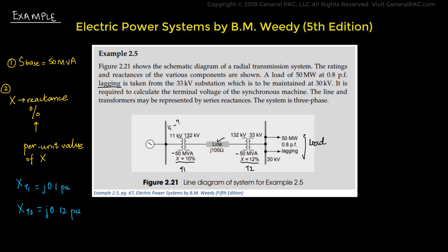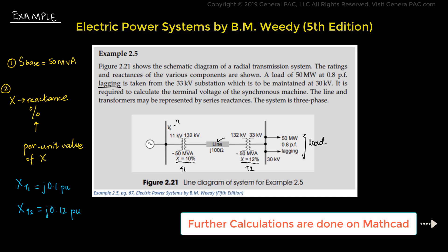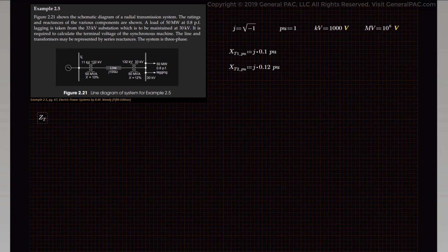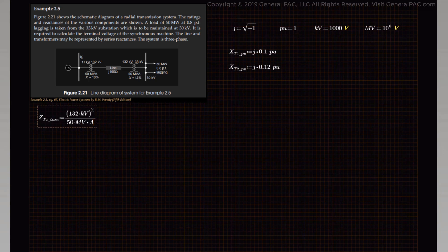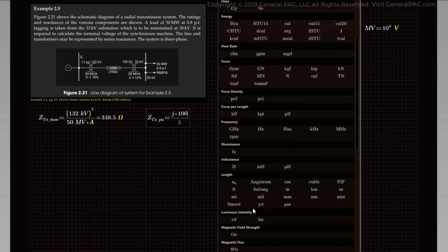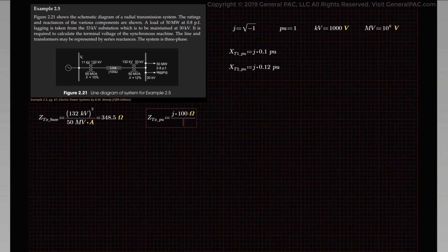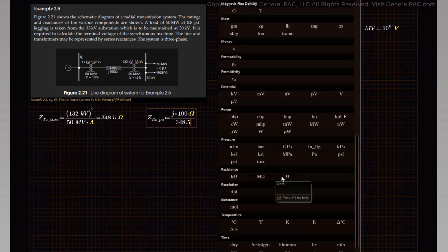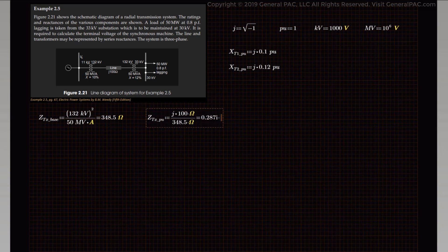Since we know the per unit impedances of the transformers, we can now calculate the per unit impedance of the transmission line. For the base impedance of the transmission line, the base impedance equals the base voltage squared divided by the base power. The base voltage being 132 kV squared divided by 50 MVA equals 348.5 ohms. The per unit impedance of the transmission line is simply the actual impedance divided by the base: J100 ohms divided by 348.5 ohms gives us J0.287 per unit.